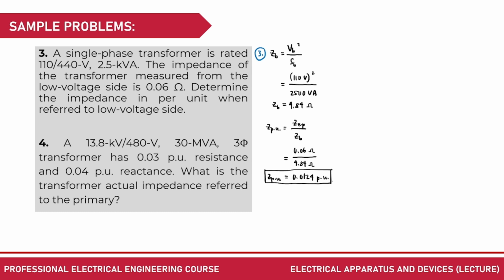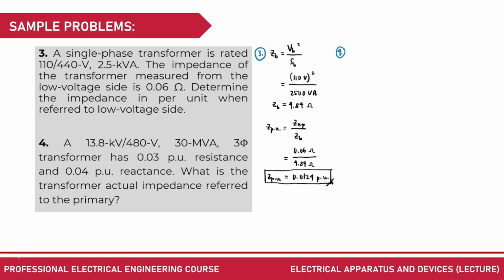Okay, basically the per unit notation is a unitless value. However, we need to put it there to understand that the value being expressed is already in per unit. Okay, next is this: a 13.8 kilovolt down to 480 volt, 30 megavolt ampere three-phase transformer has a 0.03 resistance and 0.04 reactance, both in per unit. What is the transformer actual impedance referred to the primary side?